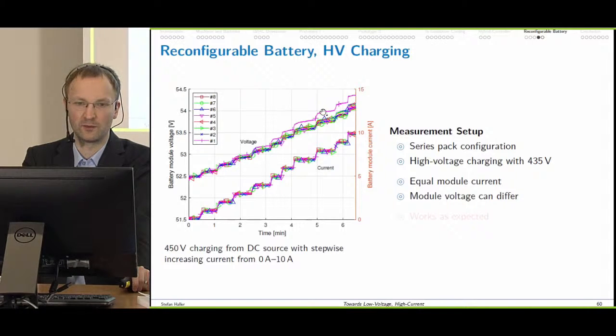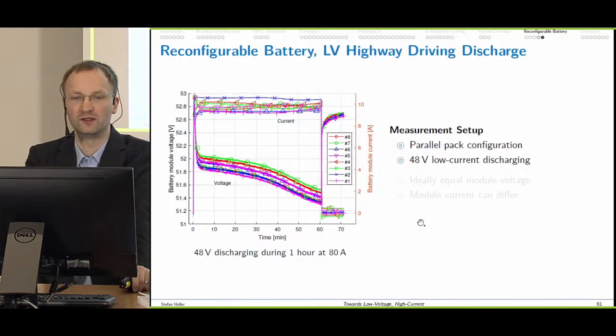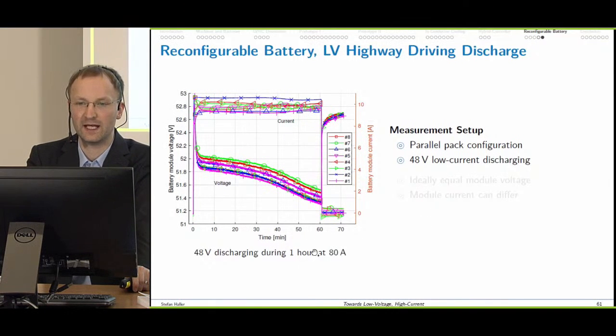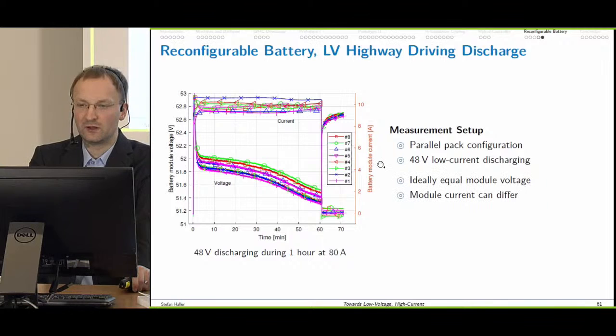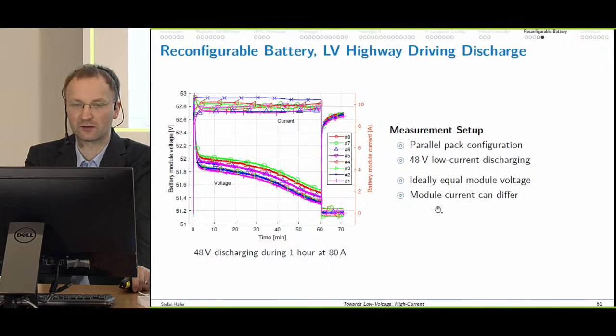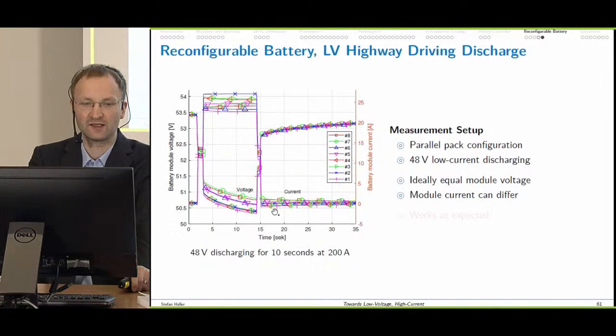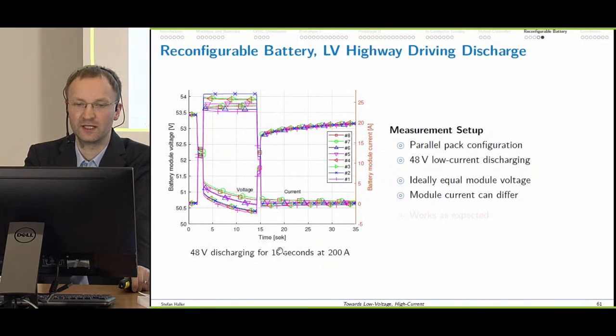We see that here, number 5 seems to reach top charge or has a high internal resistance. All in all, we can say it works as expected. Let's have a look at 48 volt discharging. This is for 1 hour with 80 amps, so 8 modules in parallel, so 10 amp per module. And it means ideally we have equal voltages at each module and the module currents may differ. And the same applies if we do an acceleration test, meaning 10 seconds discharge at 200 amp for the pack, so 25 amp per module. And we can also say it works as expected.